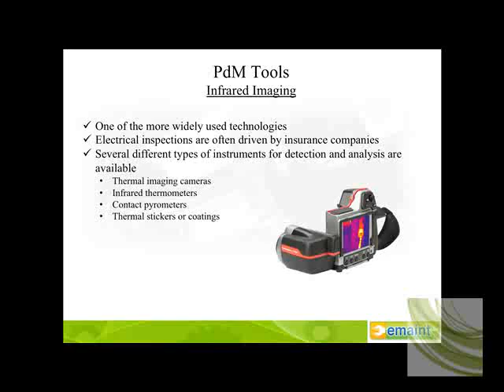Typically used on problems that would display themselves as a change in temperature, of course. And these can be one of the things that people automatically think about when they think about infrared imaging: I'm going out to find a hot spot. While that is ultimately what the cameras and the infrared imagers were initially designed to do, the opposite is true also, in that once you get accustomed to the utilization of this particular tool, looking for cold spots can tell you just as much as looking for hot spots.